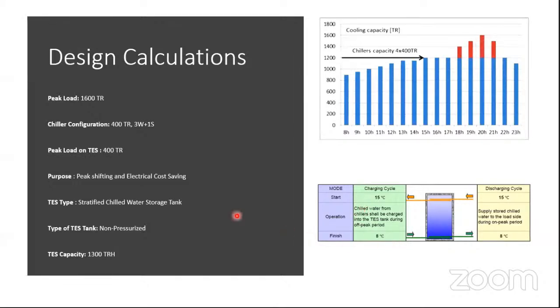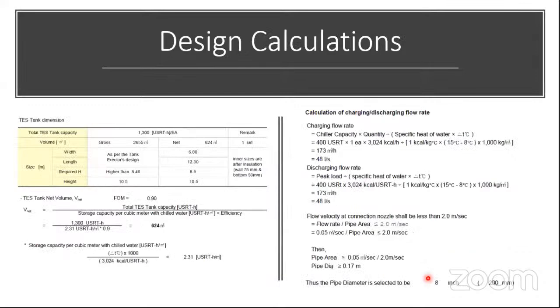In this case, with such huge storage capacities, although there are larger storage capacities also, the tank type here is non-pressurized. We will also look at pressurized though. It is designed for 8-degree supply and 15-degree return temperature. Once we have the storage capacity, the dimensions are calculated, and we can decide on the number of tanks we want to make. Here there is one tank only, or there can be multiple tanks.